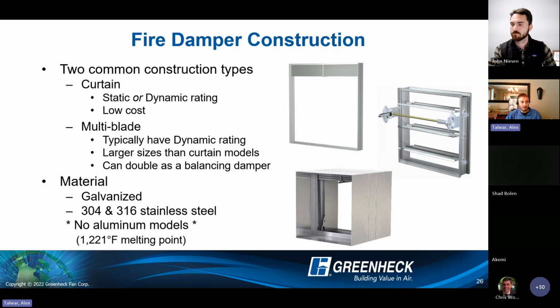Otherwise, if you do need them to close against airflow and withstand pressure, they'll come with dynamic ratings, a little bit more heavily engineered, with heavier gauge springs to help them close and stay closed. But curtain style products are certainly the most cost effective type of fire damper. But the multi-blade products do have a couple of advantages as well, right?